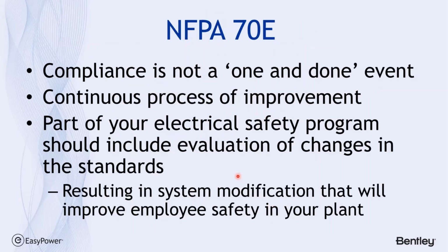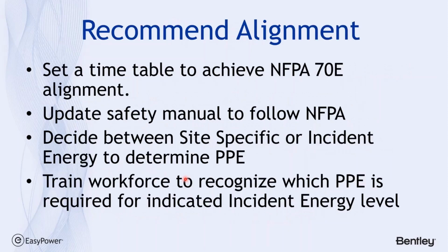So this brings up the fact that compliance to NFPA 70E is not a one and done event. It really requires the ability to include or be aware of the continuous process of improvement, both in the body of knowledge about arc flash and the equipment that's available in the industry for protection. So part of your electrical safety program should be the evaluation of the changes in the standards themselves and result in system modifications to improve employee safety. Again, my recommendation is to set a timeline to ultimately be in alignment with NFPA 70E, and then make sure you're training your workforce to recognize which PPE is required for the indicated incident energy level.